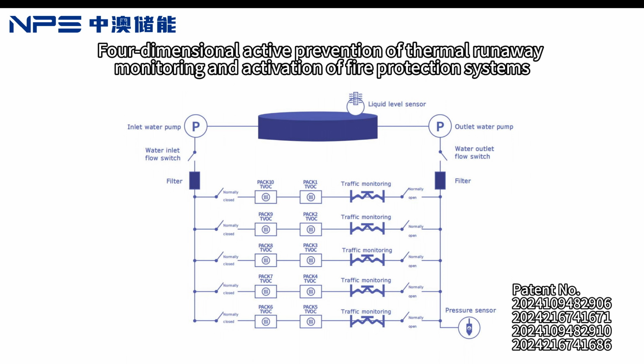To ensure that the system responds in a timely manner, a more advanced feature is that the pressure sensor on the main water line and the gas in the pipeline will also be synchronized for pressure detection of the battery thermal runaway state, to provide a composite basis for judgment.